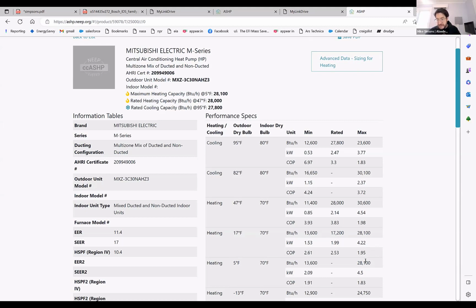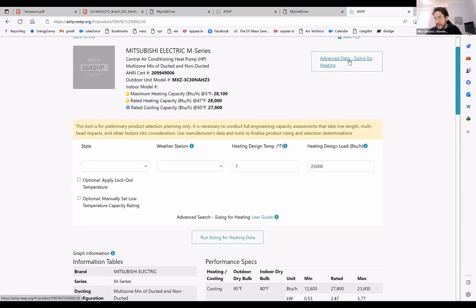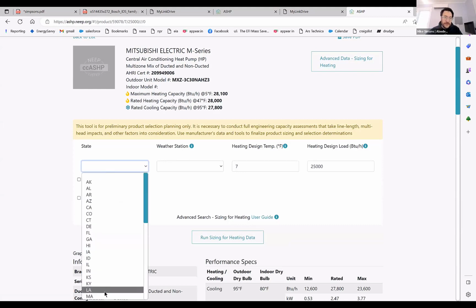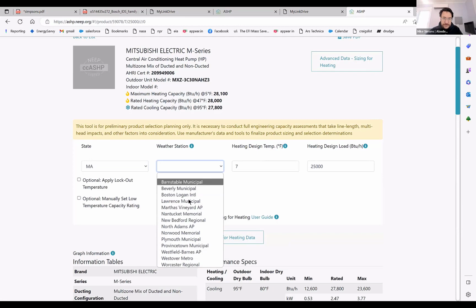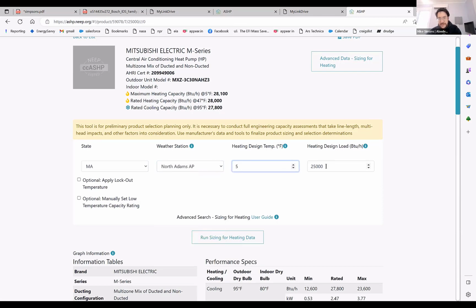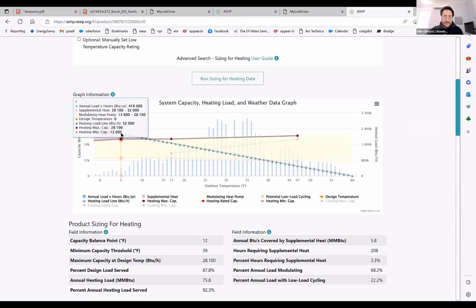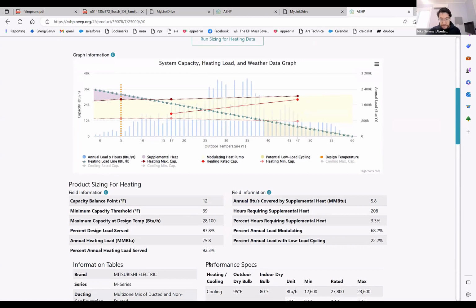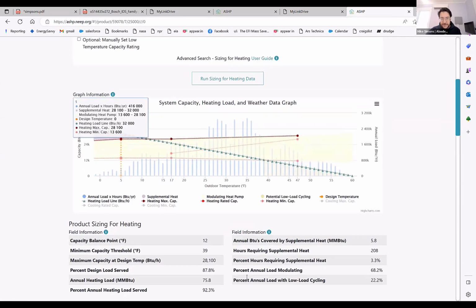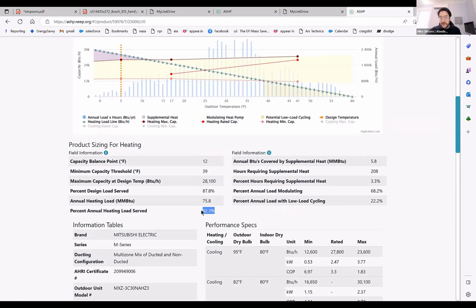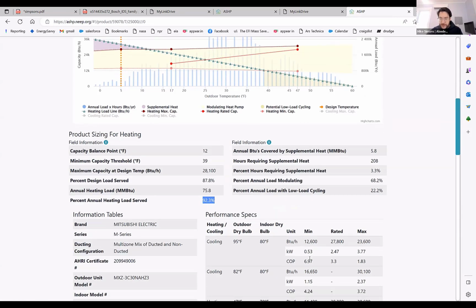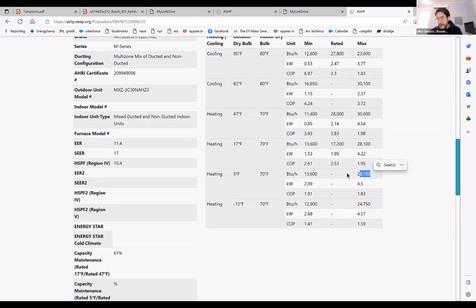One of the things I could be doing at this stage to think, is this a big deal or not a big deal, is I could push the advanced data sizing for heating. Let me go and find a central Massachusetts town. I said that it was 5 degrees and your heating load is 32,000. So if you did put in this heat pump, I would see that this heat pump system would cover 92% of the load. So it is coming up a little bit short, because we need 32 and this is 28.